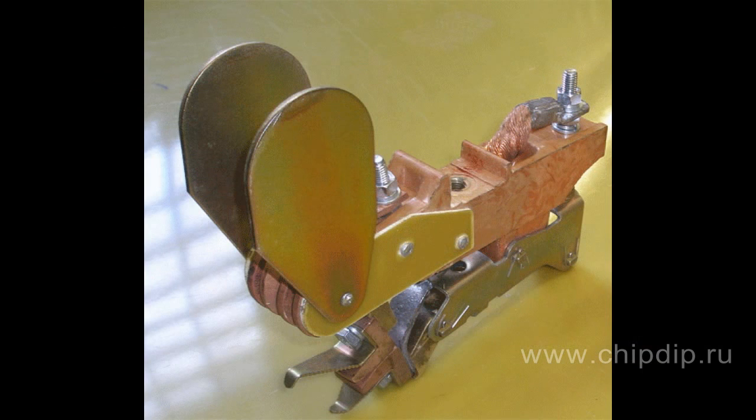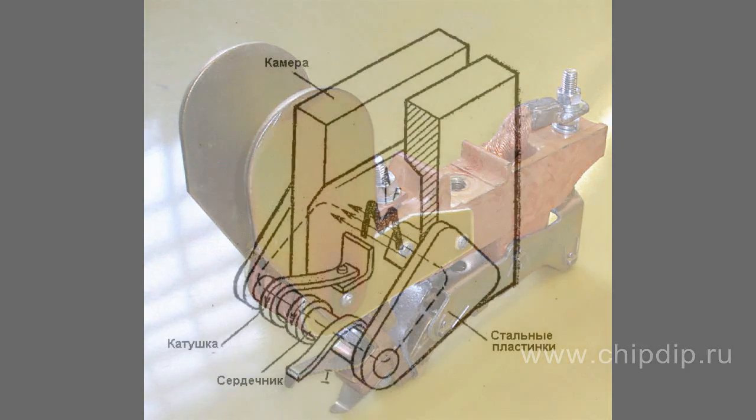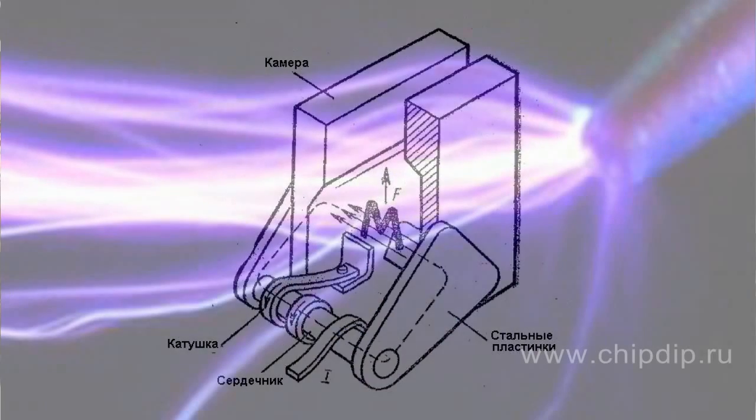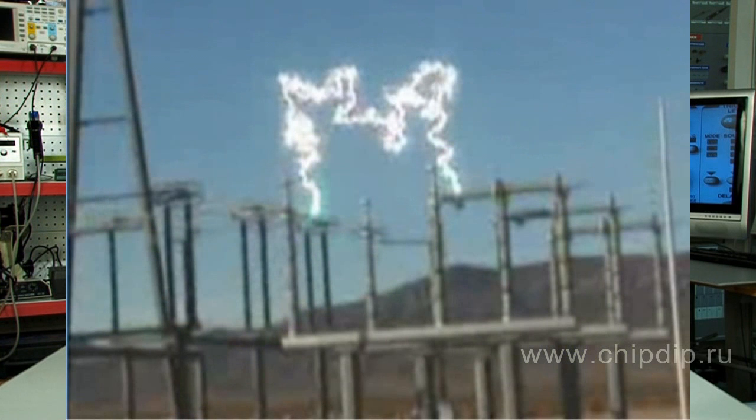Permanent magnets or electromagnets are also used in high-power arc chutes to improve the draw of the electric arc. The electric arc, emerging when breaking contacts, follows the path of least resistance. It is drawn into the slots of arc chute plates, where the plates cut it into several smaller arcs, causing it to cool and fade faster.